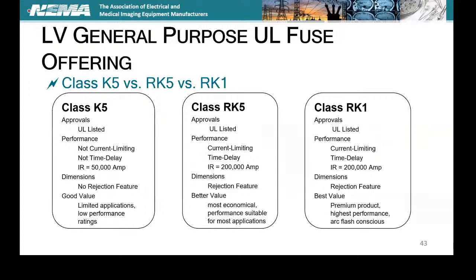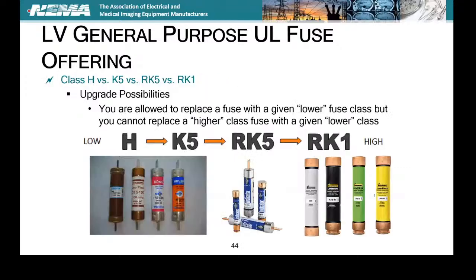If you plotted the curves for each of these, you would also see a difference. When we say things like time delay or fast acting, I'm describing the time current characteristic curve. Each one of these will have a different look of a time current characteristic curve. So all are UL listed. The interrupting rating on the K5 is 50,000, then you're 200,000 on the RK5, right?